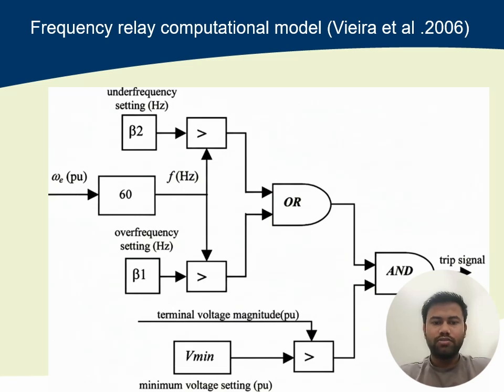Moving on, this diagram shows the computational model for our frequency relay. This is a critical protection mechanism based on the work by Vieira et al. in 2006. The relay continuously monitors two key parameters: frequency and terminal voltage. A trip signal is issued only if we hit an overfrequency or an underfrequency condition, and the terminal voltage is below our minimum setting, V minimum. This AND logic ensures that we only disconnect a generator when there is a genuine severe grid disturbance requiring immediate action, ensuring system security.